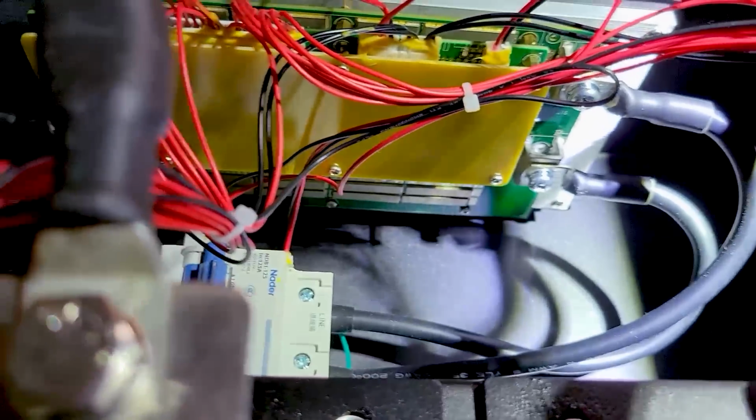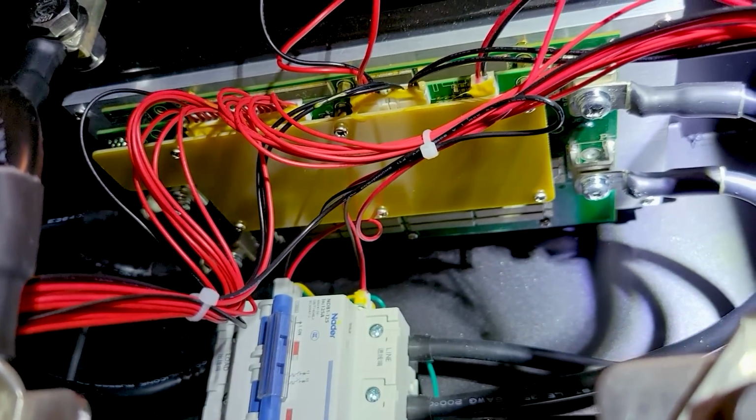I currently have 22 SolarWorld 275s on my roof with microinverters, and I am AC coupling those into this battery system. Because it didn't really make sense to take the panels off the roof, take the microinverters off, and then rewire everything to be DC coupled. It's much easier to just AC couple that into the LionEnergy system, or any battery backup system for that matter.